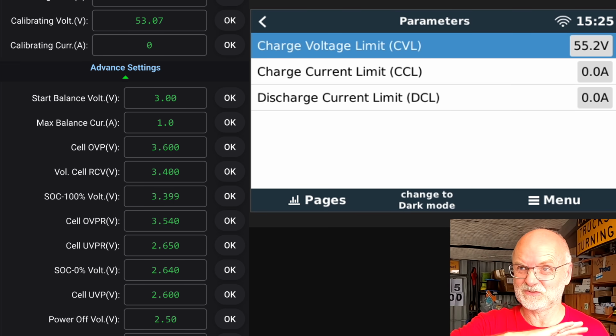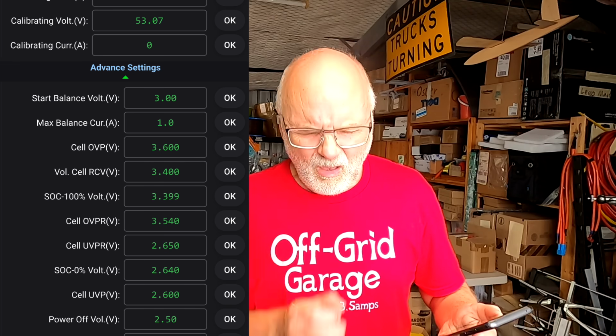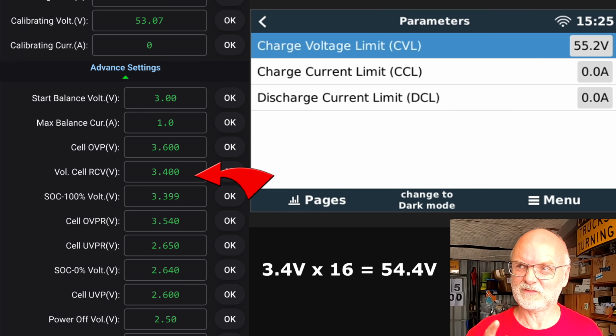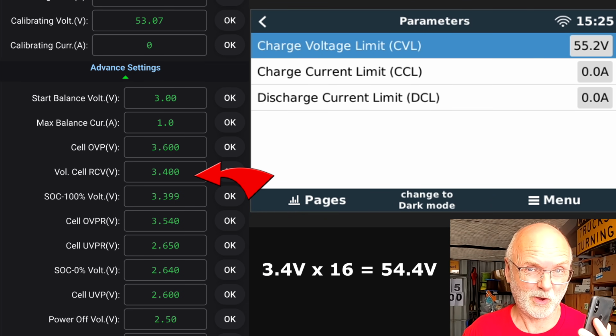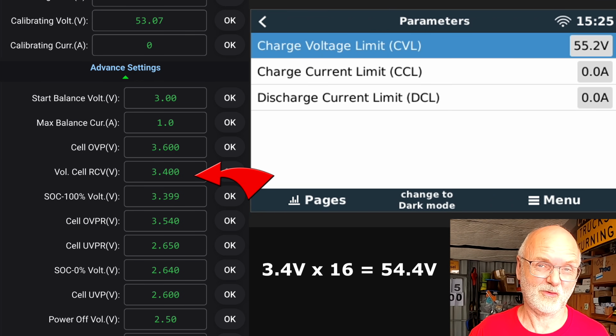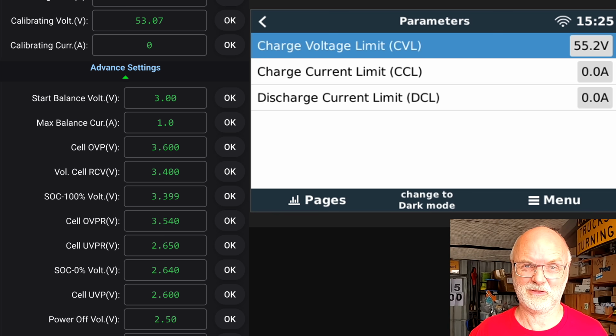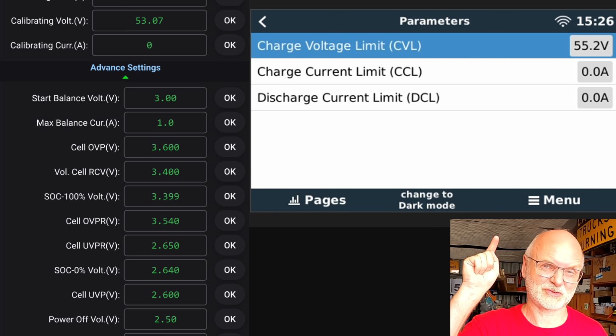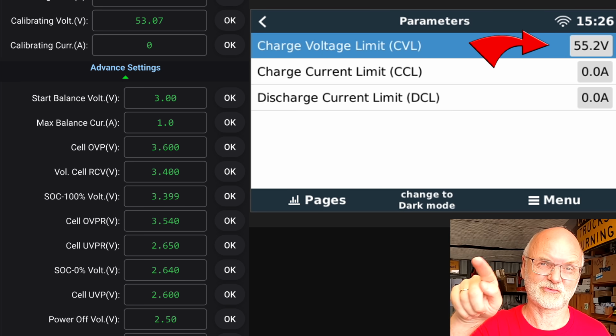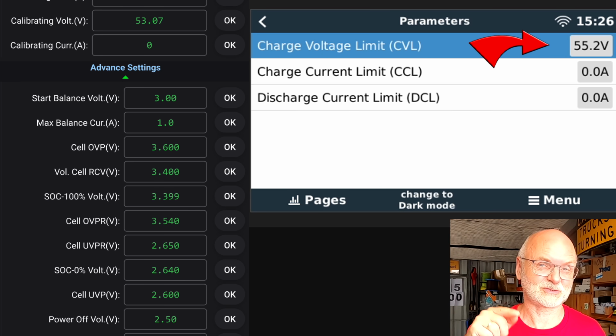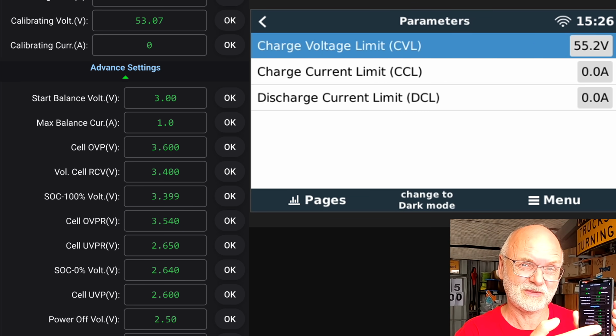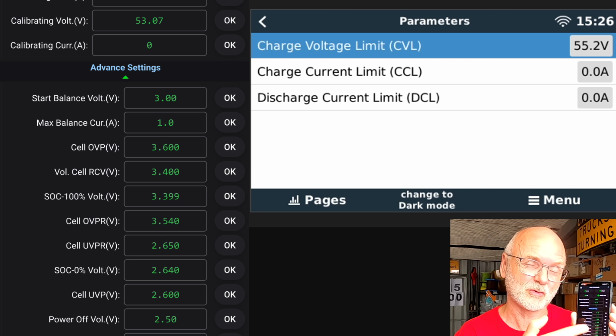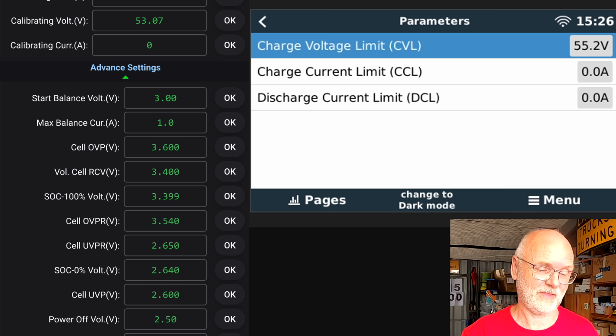Okay, it doesn't change this at all. It would only charge to 54.4. Well, it wants to charge to 54.4, but because all batteries are in parallel and the master tells your charger to charge to 55.2, it will actually charge to 55.2. So it's not using the charging settings or algorithm in the slave battery. It uses the master battery for that. And this is perfect. This is how it's supposed to be.